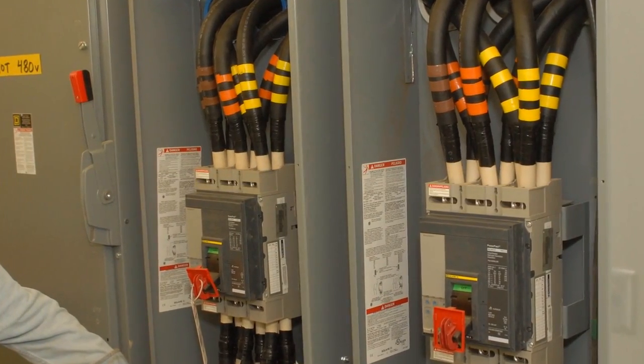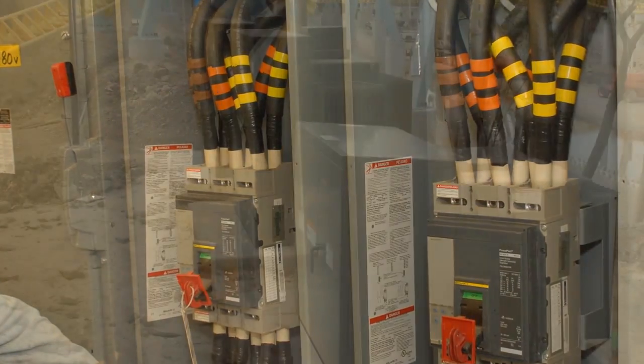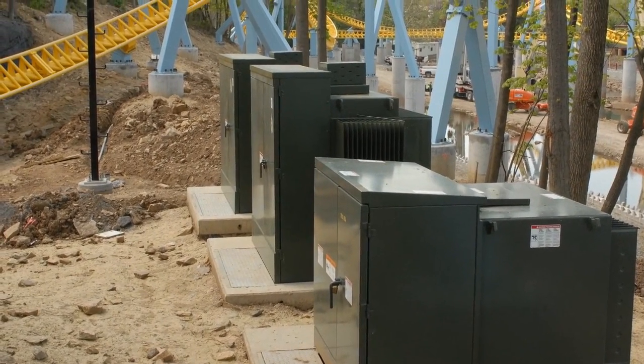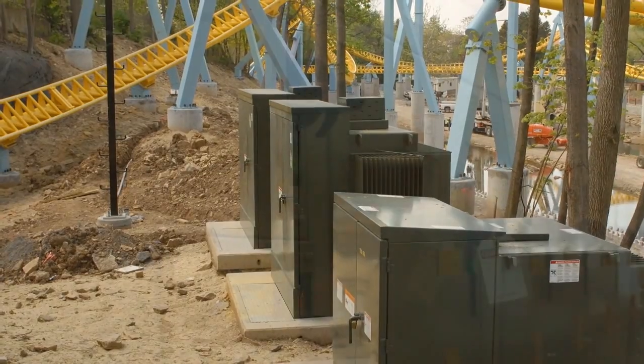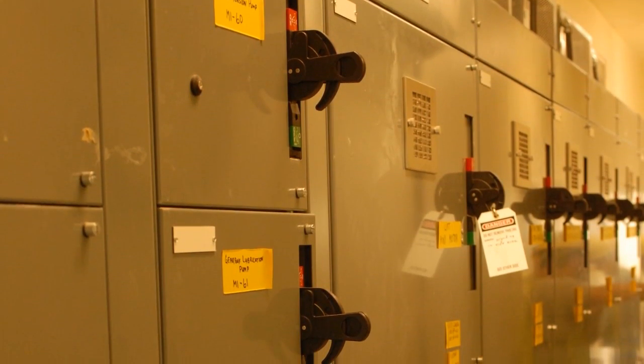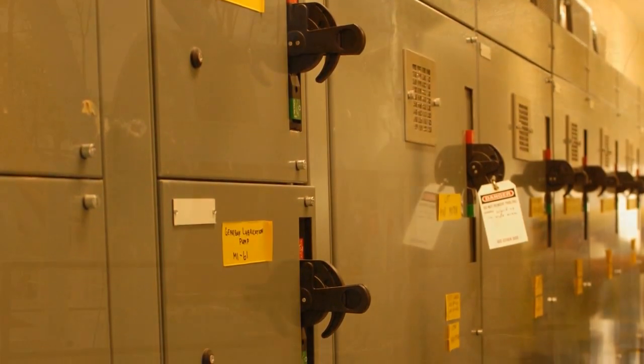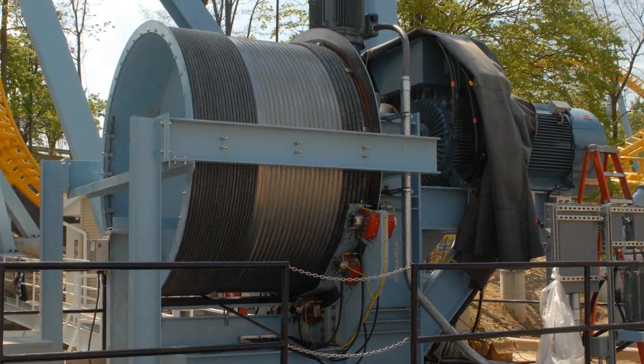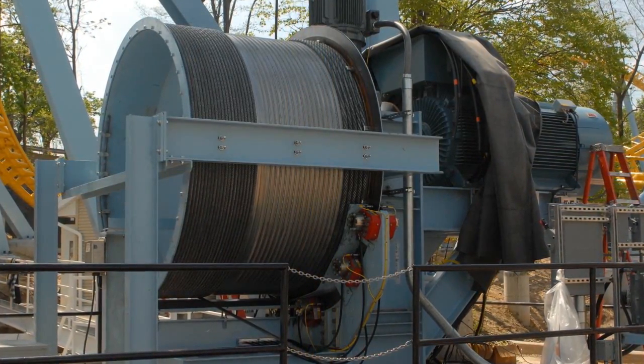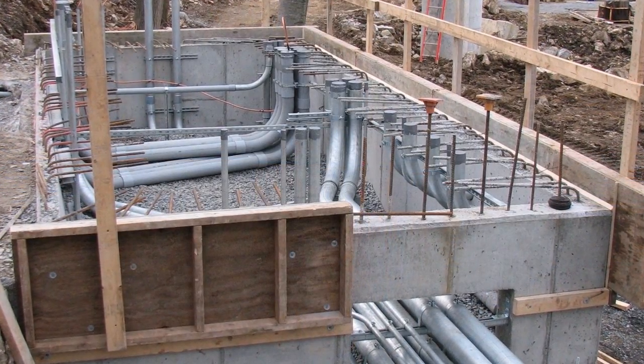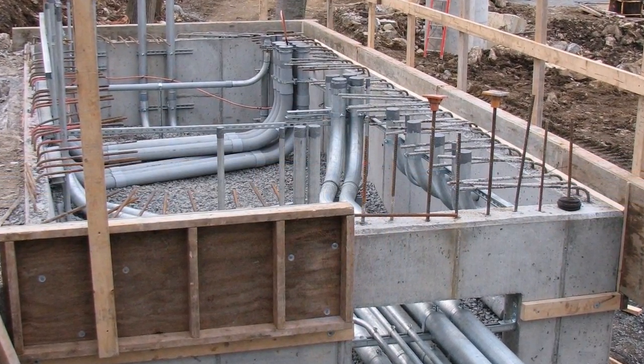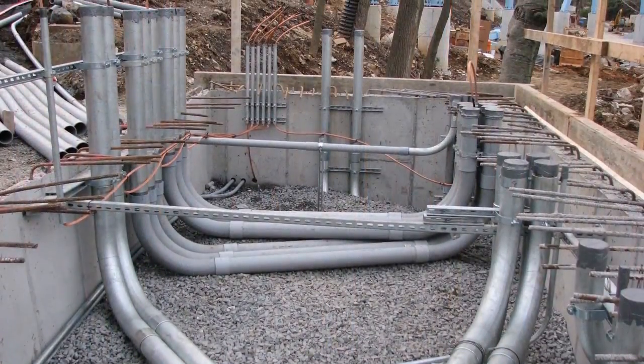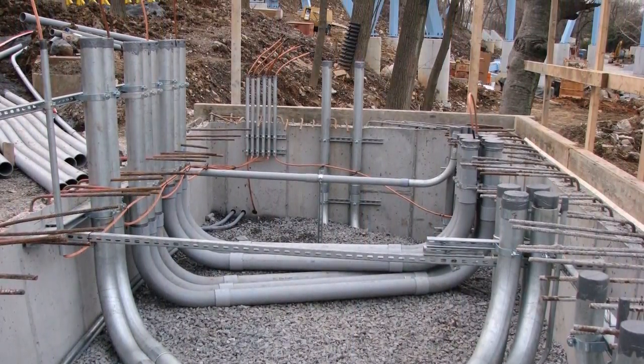The project I did was the primary power for the Sky Rush roller coaster at Hershey Park. We installed a high voltage switchgear, a 15 kV switchgear, 4 high voltage transformers, and a motor control center that ran all the motors and brakes. We installed the primary VFD drive for a 1500 horsepower motor. The main drive had 24 conduits coming up underneath it, and I had to get them all perfect because we set the main drive in place before the building was actually built.